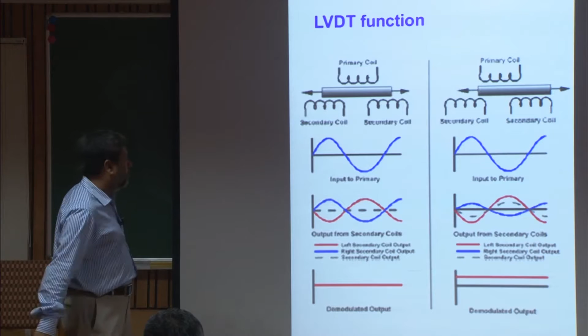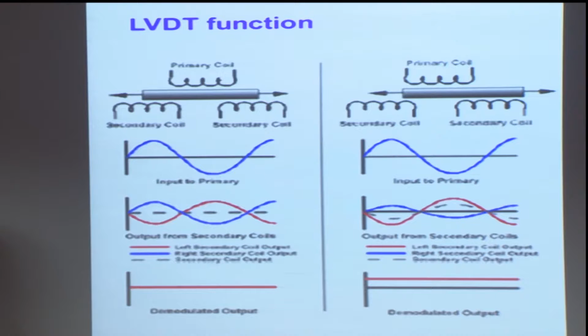Initially, the primary coil and the two symmetric secondary coils are arranged such that if you apply voltage in the primary coil while the plunger is in the middle position, the voltage generated in the secondary coils through the transformer is absolutely symmetric. But the moment the central plunger shifts during displacement, one secondary coil gets more core area and the other gets less core area, immediately creating asymmetry in the voltage generation. It's a simple system, but very effective and very robust. This is the function of an LVDT sensor.